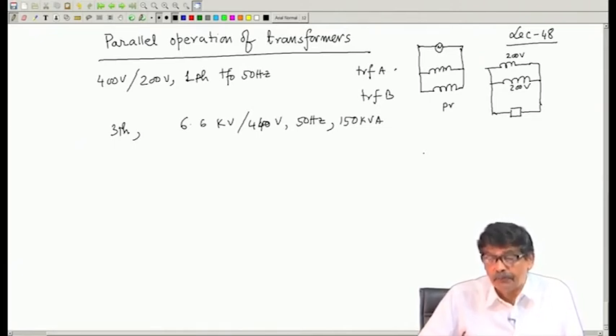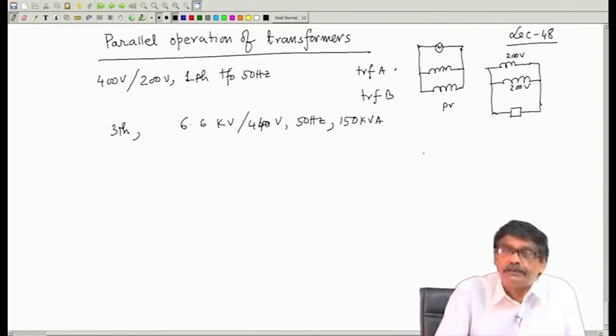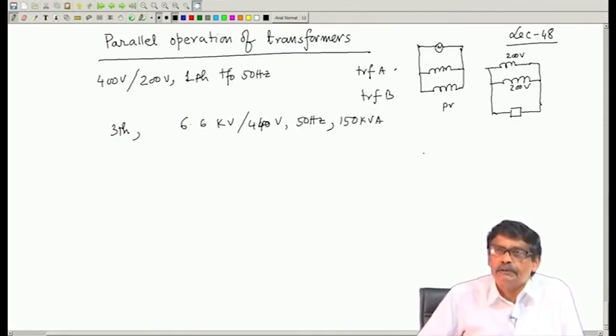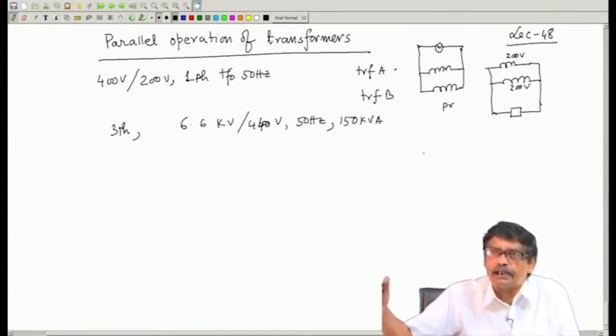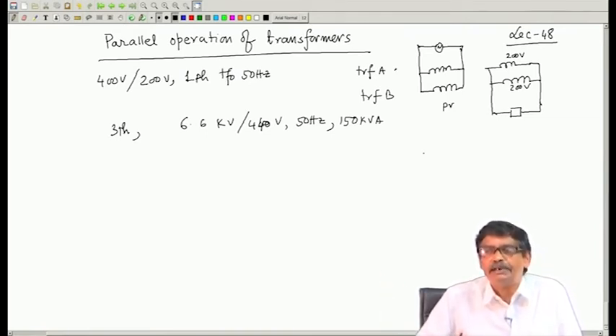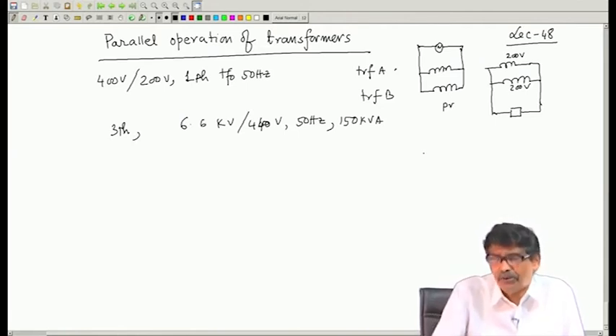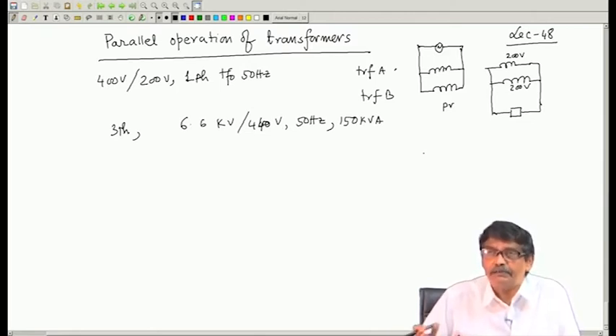Therefore, perhaps another alternative is that you purchase another transformer of similar rating and connect them in parallel, so that the combined kVA is 300 kVA and it will last for another 5 or 7 years. After that, perhaps another transformer. So, your cost of investment is reduced, since you do not have to purchase a very big transformer at one time, and this is a very practical solution in some areas.